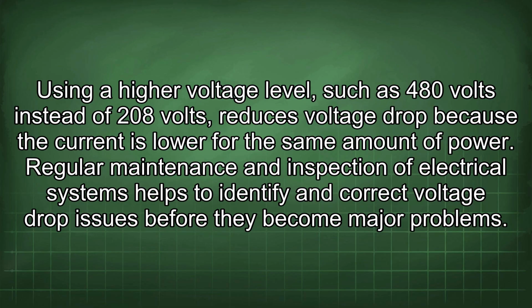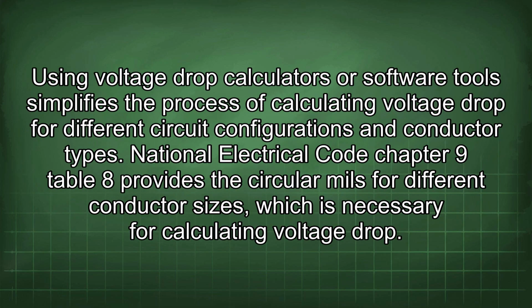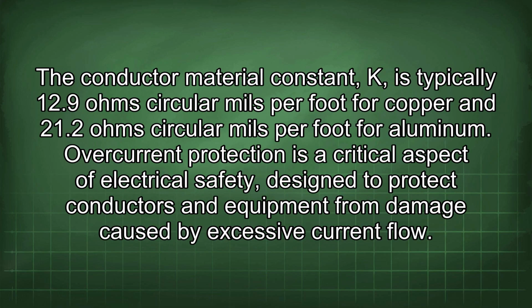Using a higher voltage level, such as 480 volts instead of 208 volts, reduces voltage drop because the current is lower for the same amount of power. Regular maintenance and inspection of electrical systems helps to identify and correct voltage drop issues before they become major problems. Using voltage drop calculators or software tools simplifies the process of calculating voltage drop for different circuit configurations and conductor types. National Electrical Code Chapter 9 Table 8 provides the circular mils for different conductor sizes, which is necessary for calculating voltage drop. The conductor material constant, K, is typically 12.9 ohms-circular mils per foot for copper and 21.2 ohms-circular mils per foot for aluminum.